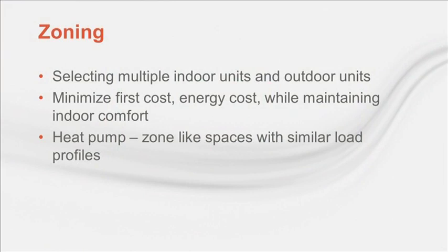In order to optimally zone a VRF system, it's necessary to know the design, heating, and cooling load in each zone. Designers can still zone a system without the loads, but the performance will not be optimized and comfort could be sacrificed. Good zoning allows the choice of a heat pump or heat recovery system. As was explained earlier, the VRF heat recovery unit can provide heat to some zones while providing cooling to others. But the VRF heat pump will only heat or cool its zones and stay in either heating or cooling until all zones are satisfied. Only then the heat pump will be allowed to switch mode and attempt to satisfy the other zones. So, zones of a heat pump system must be similar in load characteristics in order to maintain comfort.